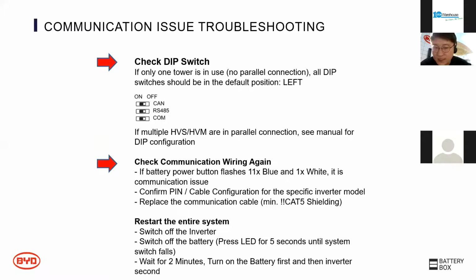If you see the battery flashing 11 blue and 1 white, it is definitely a communication wiring issue. Please double confirm your communication, because communication is very important to get the system working properly for the next 10 years, and we don't want to risk anything if the communication isn't okay. The battery will tell you the communication isn't working, so please double check on this.